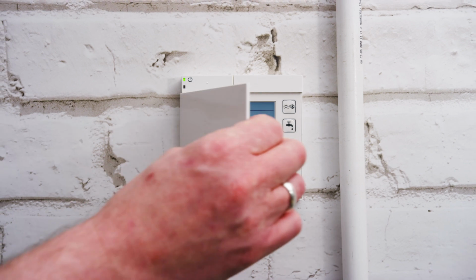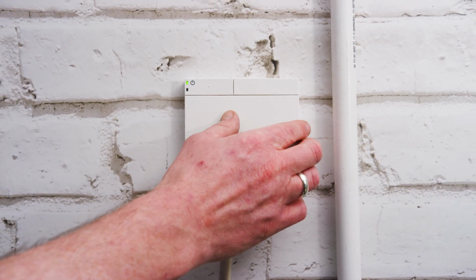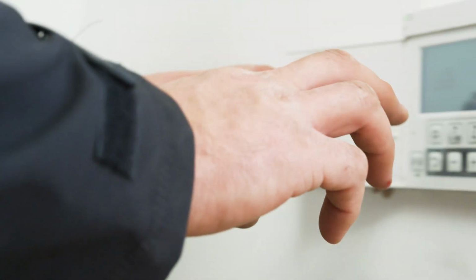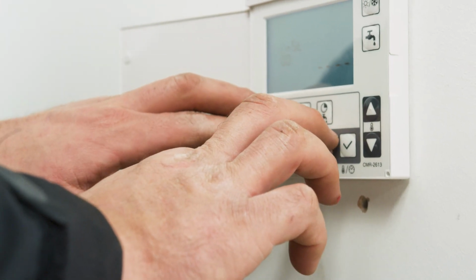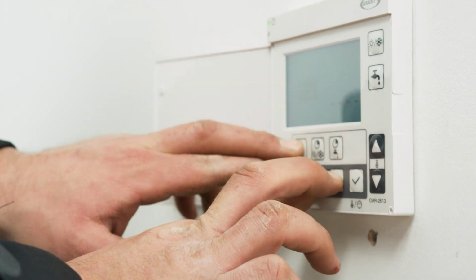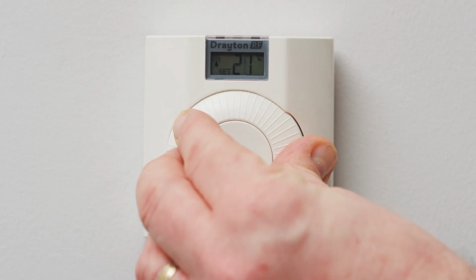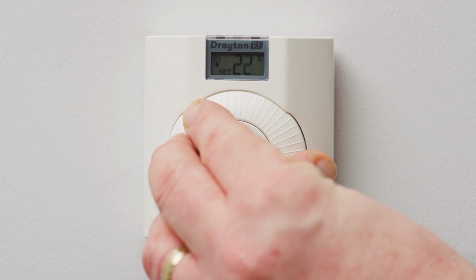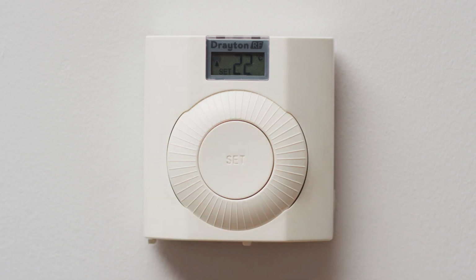Finally, it is important that the heat pump controller is not tampered with after commissioning, such as trying to raise the temperature from the unit to achieve a greater temperature at the radiators. The controller should be left as set by the installer to ensure that the system operates correctly. This will help maintain the desired comfort levels within the property and help the heat pump work most efficiently and effectively. The room thermostats and the thermostatic radiator valves should be used to manage the desired temperature within the property.